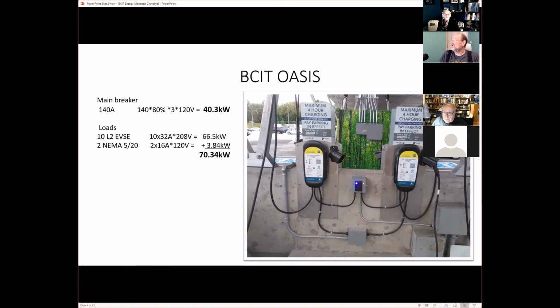What we wanted to do is install 10 level 2 chargers, plus 2 120 volt outlets with a NEMA 5-20 plug, like the plug in your kitchen. That's 70 kilowatts of load. So we've definitely way overloaded our panel.